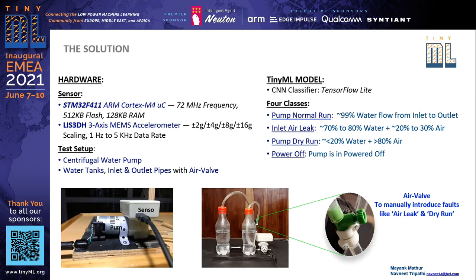The model that we built was a CNN convolutional neural network classifier with four classes to classify from: whether the pump is running normal, or it has any fault like an air leak, or a pump dry run, or whether it's powered off.